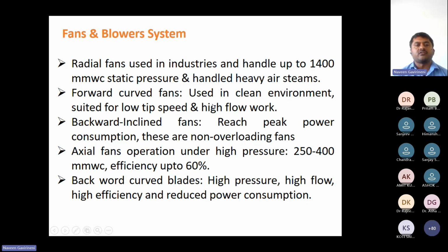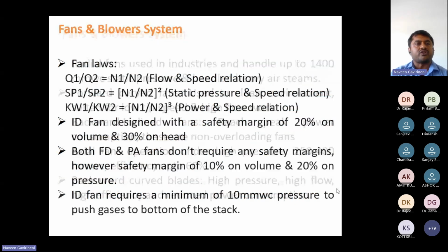We are using only backward inclined fans. Why? Because forward curved blades are meant for clean environments and high flow work, but we are not using that much flow now. So we are using backward curved fans. Axial flow fans are meant for the PA fans, which I have already explained, since so much air quantity is needed for that. Backward curved fans give high pressure, high flow, and high efficiency with reduced power.